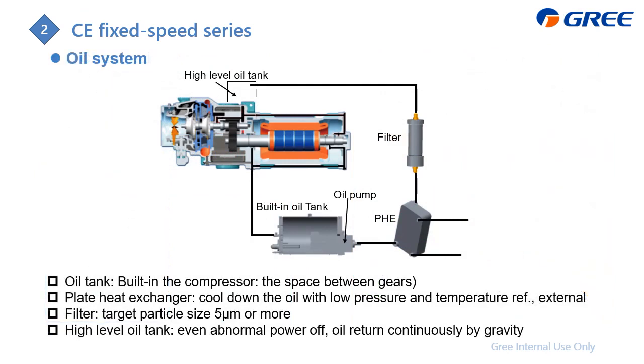Next is the oil system. First, I will introduce how the oil flows inside the CE series. First is from the oil pump. The outlet of it is hot oil, which goes through the plate heat exchanger to cool it down. Then this oil goes through this filter, and then to the oil tank located here, and then it separates into two passes. First is to the front, and the other is to the rear, going through the motor for lubrication and also for the shaft. After that, it collects some heat, and its temperature becomes higher, so it becomes hot oil and flows back to the oil tank. It's also built in inside the compressor. And then it goes through this again.